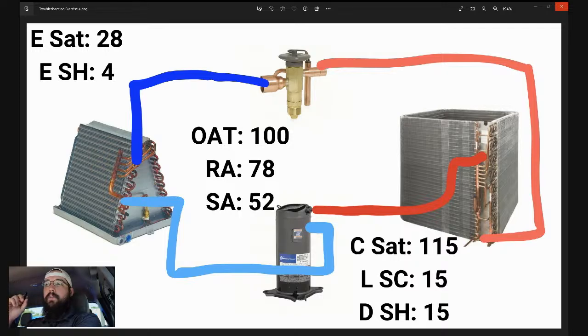I would also venture to argue, even if we did have a restriction in our supply, would our external static still be that high? Because you've got to think about where we are taking our static readings. We're talking a regular split system air handler here, say a little 5-ton. So we take pre-filter static right there at the duct, and a post-unit supply reading as we're coming out of the supply trunk. Those two statics give us our external static.